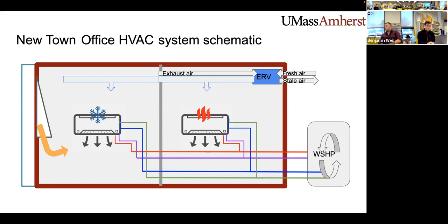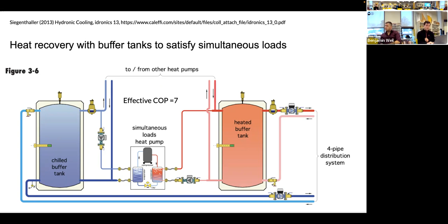So how would this heat trading work? Well, you use two separate tanks, a chilled and a heated buffer tank, for a heat recovery system that will be used to satisfy simultaneous loads. This is the most common operating mode for the office during all but the coldest periods, and will represent about 1/3 of the heating for the church by supplying excess heat from the offices directly to the church.